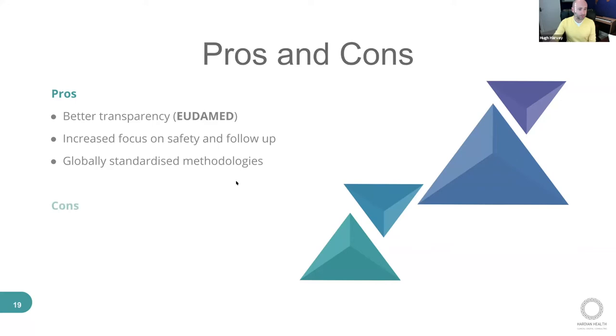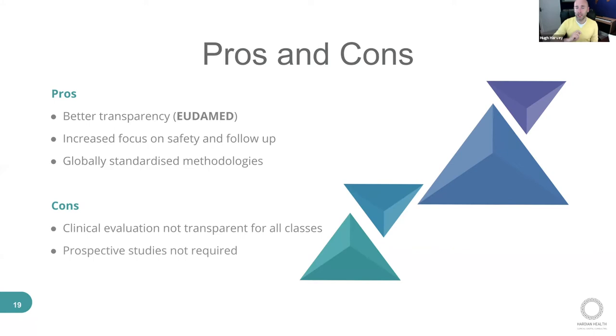There are some cons though. You don't have to publish your clinical evaluation, and you don't need a clinical evaluation for low-risk devices, so a little less transparent on that front. And you still don't need a prospective study to get regulatory clearance. This is true both in America and in Europe, though it still raises eyebrows from clinicians, who sometimes demand prospective studies before they buy. There is yet to be a set piece of guidance, though I'm assured one is coming, on what data quality you need for your validation studies. That's why I'm helping with this, because they're really focused on it - what does good quality data look like in terms of validating an AI system?